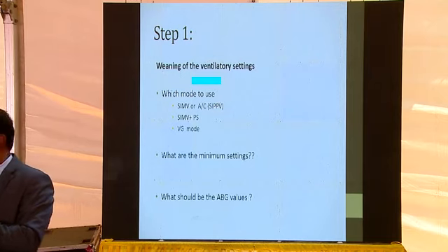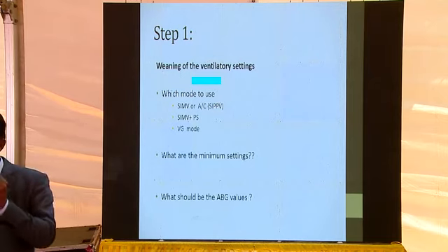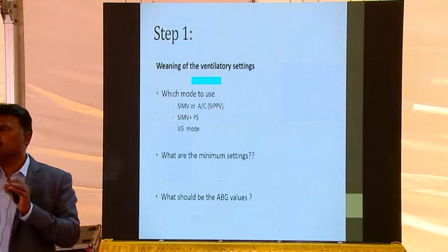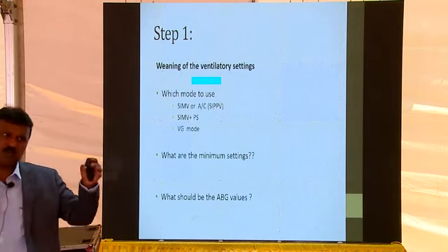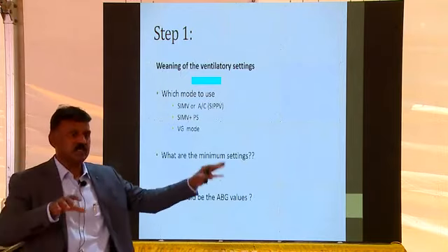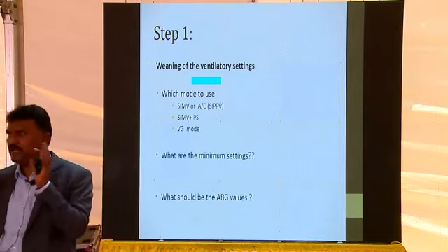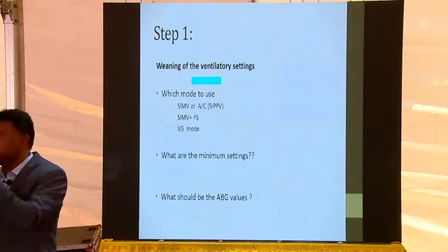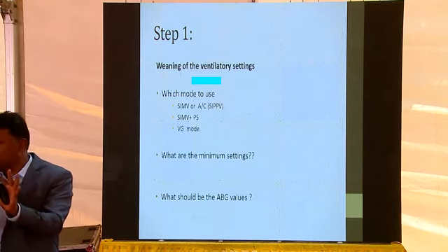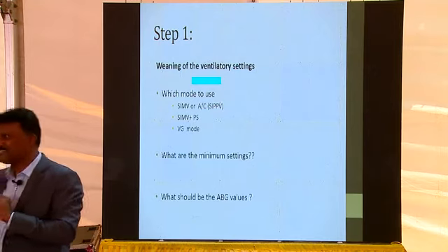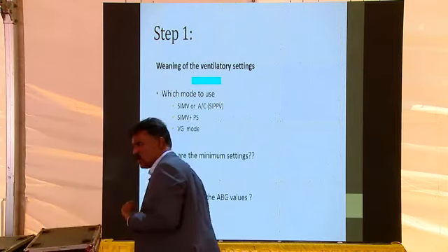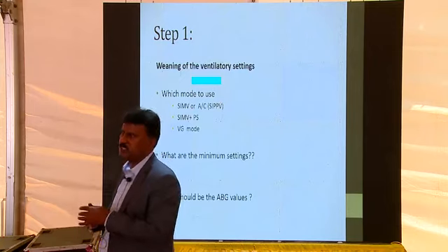It's a little boost; he decides his own inspiratory and expiratory time. It gives a small boost which will help him support these 40 breaths. It's sort of assist control, but not completely supported. In SIMV plus pressure support, you are supporting around 20 breaths, and the remaining spontaneous breaths are supported by pressure support. That's another mode people have been fond of.